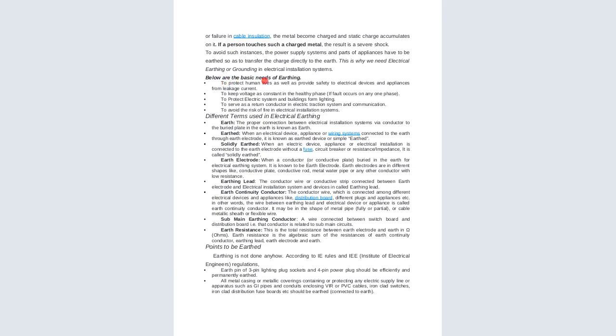Below are the basic needs for earthing: to protect human lives, to keep voltage constant in a healthy phase if a fault occurs on any of the phases, and to serve as a return conductor in the electric traction system in communication. Another one is to avoid the risk of fire in electrical installation systems. Now, different terms are used in electrical earthing, that is the earth. What is the earth, you might ask? An earth is the proper connection between the electrical installation system via the conductor and the buried plate of the earth. What is earthed? It's a term that we are also going to find.